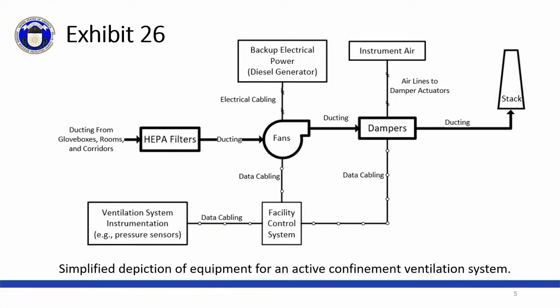So the active ventilation system already in place, which is safety significant, not safety class, already has significant redundancy and actually is highly reliable. We see that manifested in the operations of the plant. The upgrade strategy that you mentioned to the ventilation and support systems focuses on replacing major components, such as some of those illustrated in that flow diagram, to achieve a more robust ventilation system. This is going to be done by proactively managing obsolescence, increasing seismic performance, and in some cases, adding further redundancy. And in fact, in some cases, those actions have already been taken.